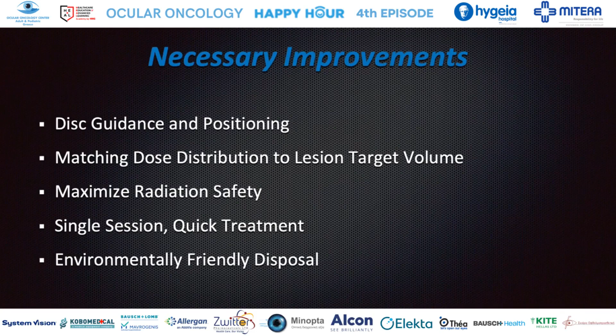Let me introduce our ophthalmic applicators. The I-wand-A was built for anterior ocular use. The shielding module is located at the tip, where radiation shielding is most effective, surrounding the disc source. The I-wand-P doesn't need the shielding module as it sits behind the beta radiation absorbing eye. Plus, the I-wand-P has built-in lights to assist the surgeon moving it into and documenting proper position during treatment. The I-wands are pre-sterilized for single use.